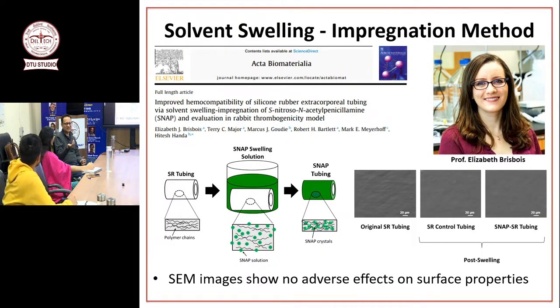Now you have a NO releasing material ready without extruding, without making a film or whatever, and it's very uniformly distributed inside the wall of the tubing, and you have a NO releasing surface ready. So now you can pick an existing tubing, an existing catheter, and make it NO releasing.